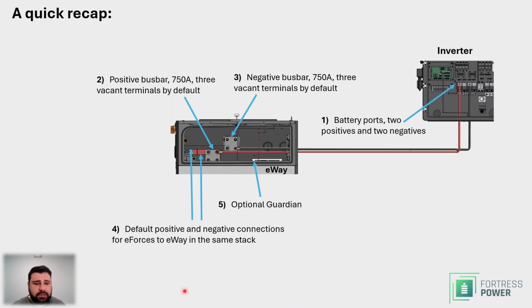Let me use a laser pointer. So positive to the eForce units in the stack, negative to the eForce units in the stack. That leaves you with 1, 2, and 3 vacant ports on each bus bar. In this case, these 2, because this picture shows the inverter already connected to the eWay. So that's your positive and that's your negative. And you see the optional Guardian.